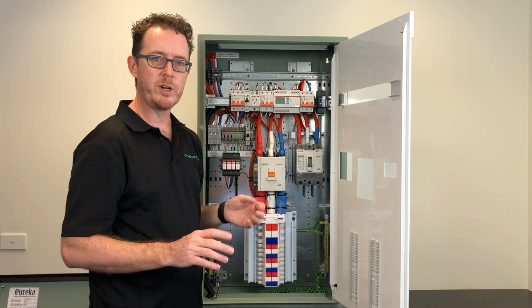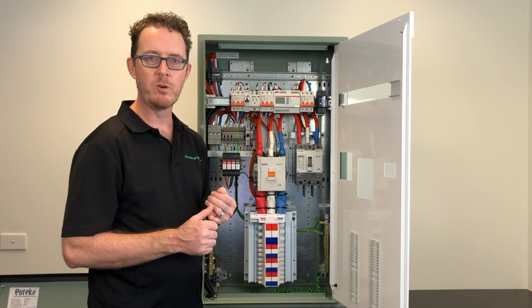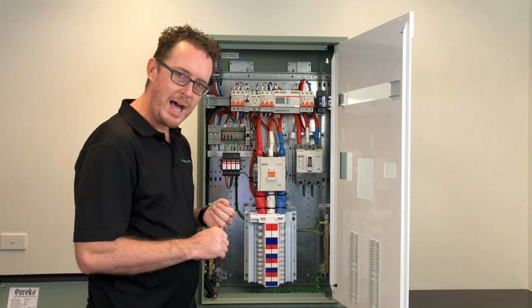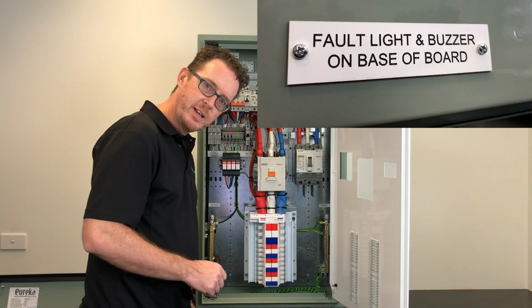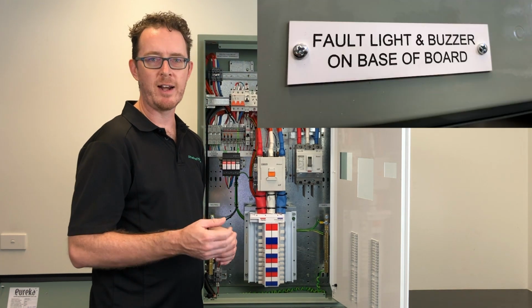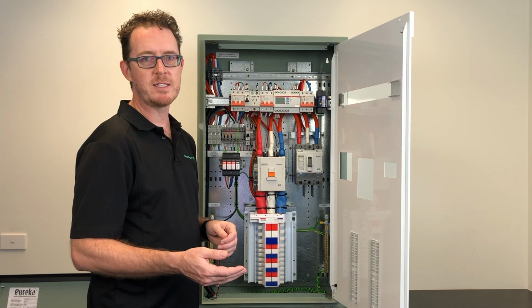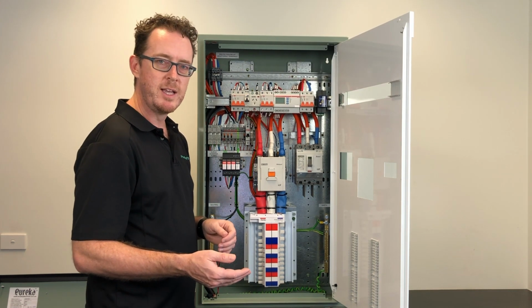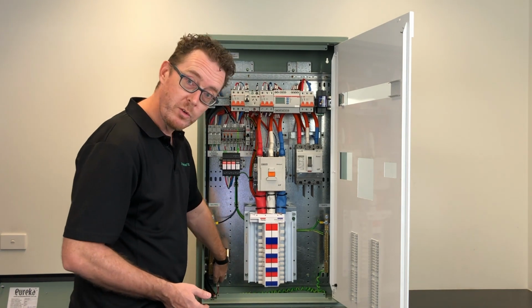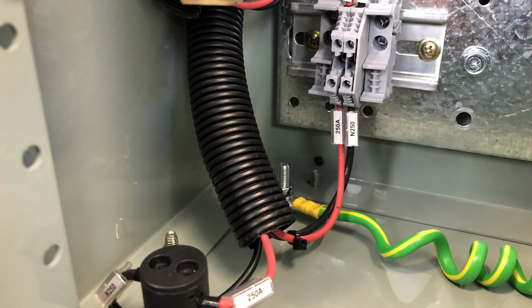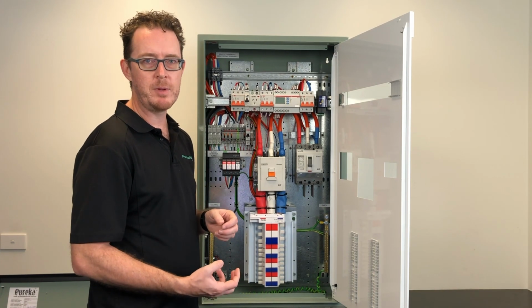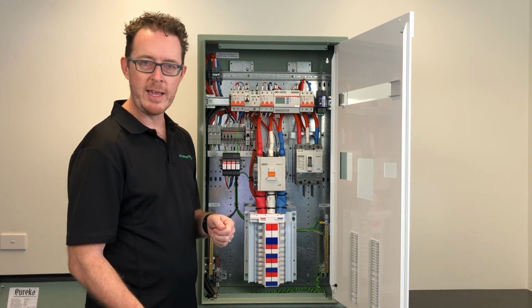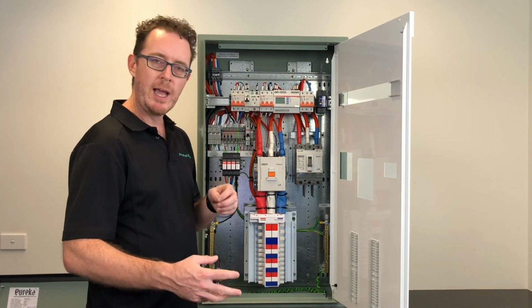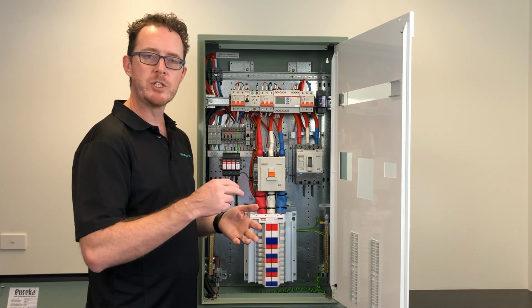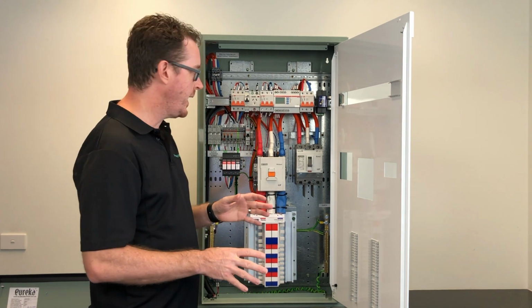One of the things that we've done, for example, is we have a red light with an audible alarm on the base of the unit, but because that goes through the gland plate and we want to make sure that the installation is convenient for our customers, that has terminals inside, so you just need to remove 2 screws, and then the wiring to that light and audible alarm is disengaged, and it's easy to remove the gland plate with that light in situ, and then later, as you put the gland plate back on, just put the wires back into the terminals, 2 screws, and it's done.